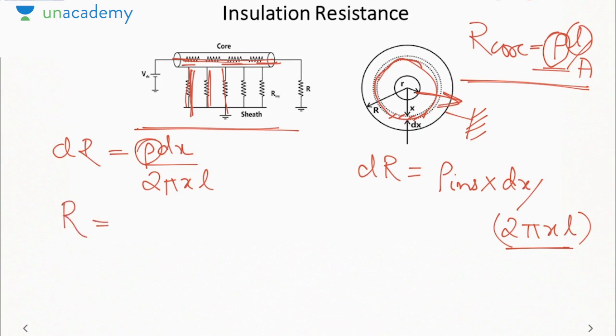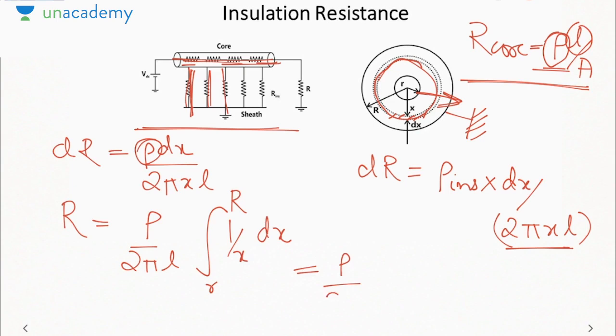Now to determine the total resistance, we will integrate this from small r to capital R. So it will be rho by 2 pi L, and the integration of 1 by x is log x, so ln R by r. Remember, this is the total resistance in ohms. Do not get confused that since we have divided by the length, it represents the resistance per unit length. No, it represents the total resistance of the insulating layer in a UG cable. Now if you see, as we increase the length, the insulation resistance will go on decreasing, so it varies inversely with the length. This is the most important relation when it comes to insulation resistance. Even if you do not remember the entire expression, just remember that it is inversely proportional to the length.